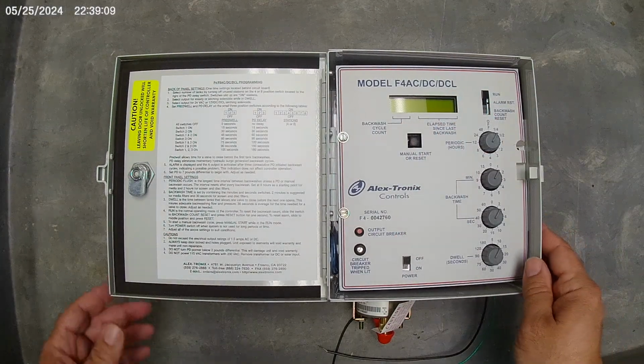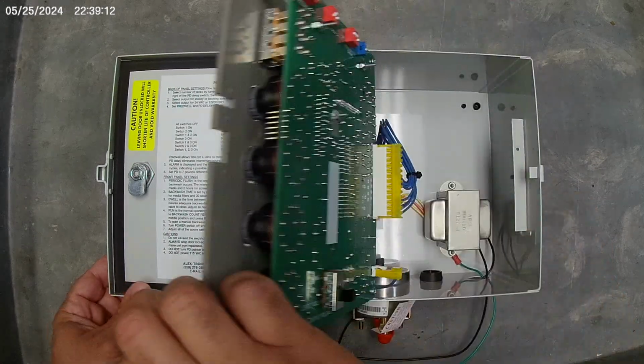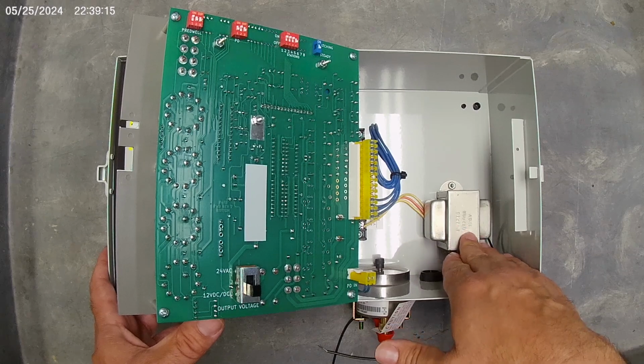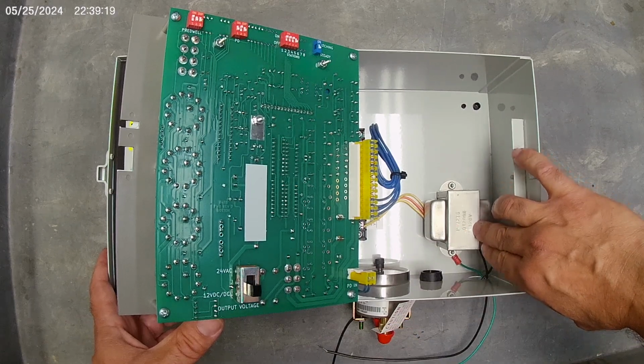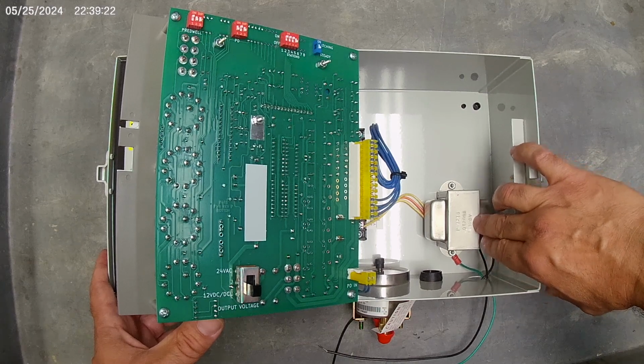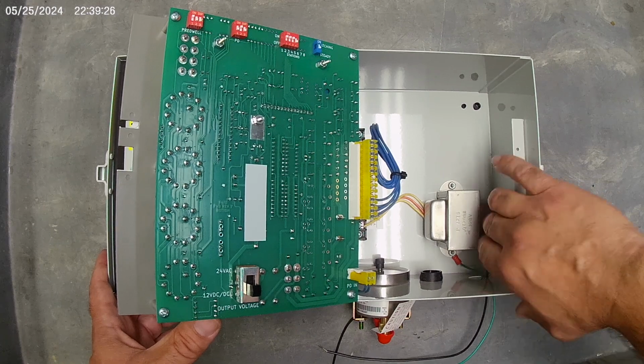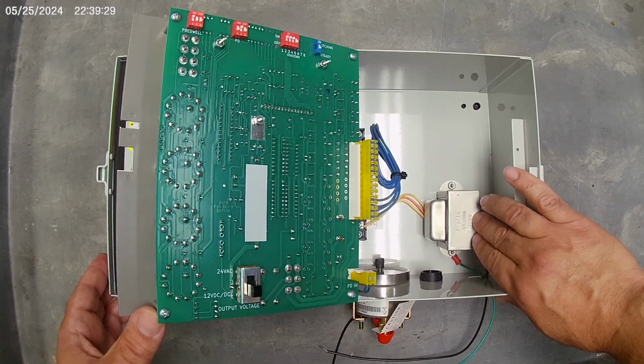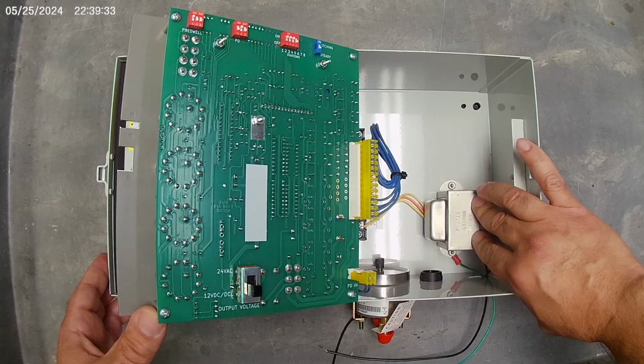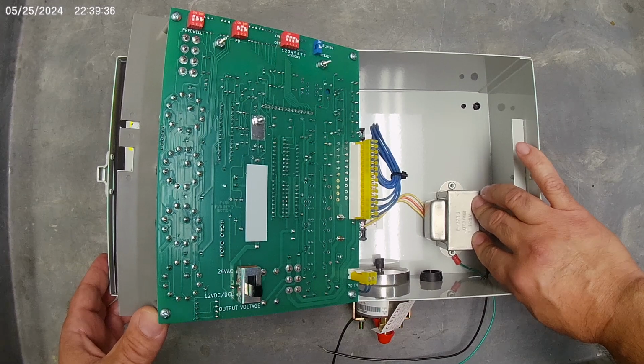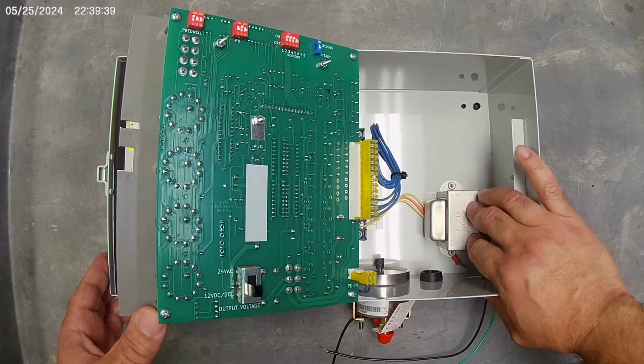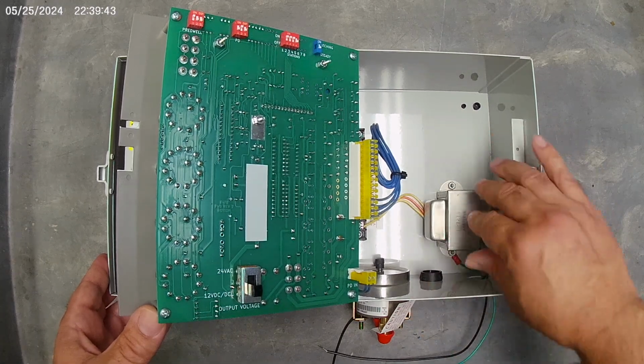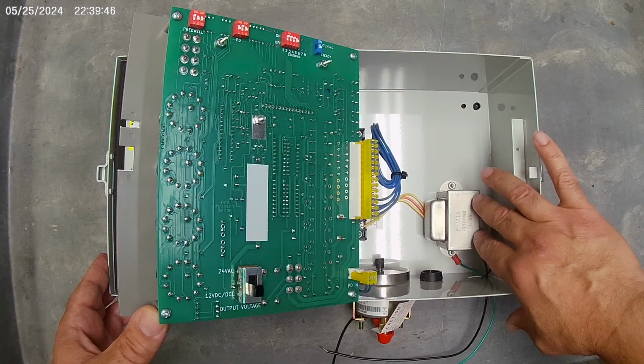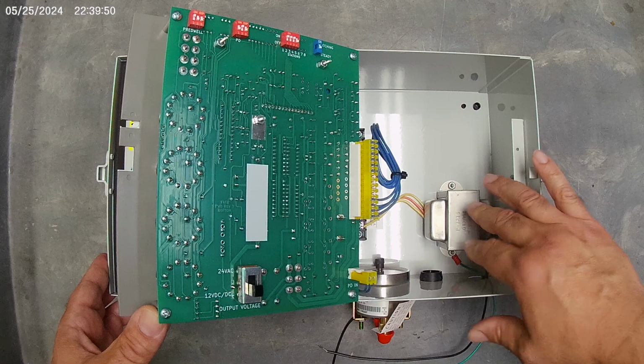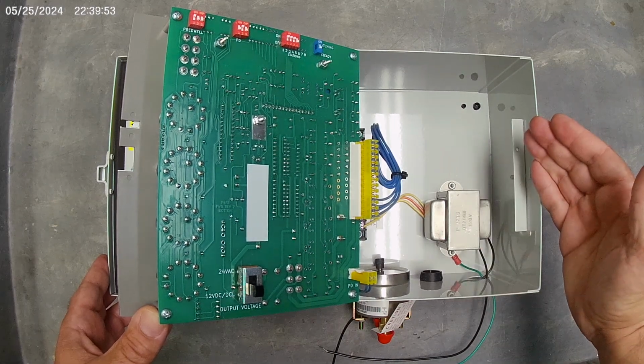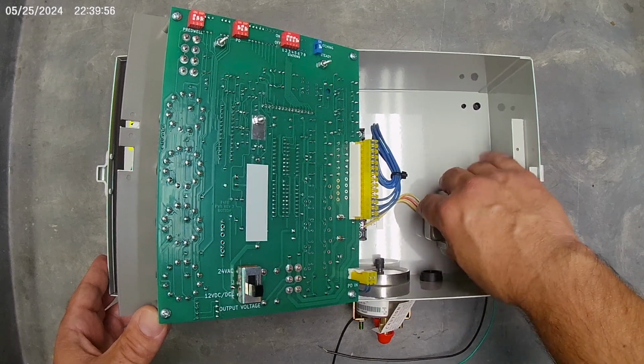The most common cause of failure we have on these controllers is on our initial setup, wiring the transformer into a voltage it doesn't want to see. Within the last 15 years, our transformers have the voltage directly stamped right on them. For example, this one's 120 volt AC. That's all it wants to see on the input. We do find situations where people wire these into VFDs, not realizing they're wiring them into VFDs, and they don't like that. You get real erratic behavior or just burning up of the controller. Additionally, people sometimes will wire this to a stinger, 170 volt stinger, or a 120 volt transformer into a 240 volt circuit, which of course immediately burns up the transformer.